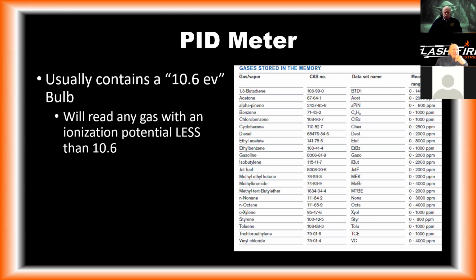And then there are a variety of gases that wouldn't be. So usually we're going to have a 10.6 eV bulb ionization potential, and that's what you guys have. So it will read any gas with an ionization potential less than 10.6. So if you're presented with, say, an MSDS sheet from the manufacturing facility, it may say on the MSDS sheet what the ionization potential is. If not, you could look it up in your Wiser app or your NIOSH book, and this would be able to narrow down which gas you're potentially reading.